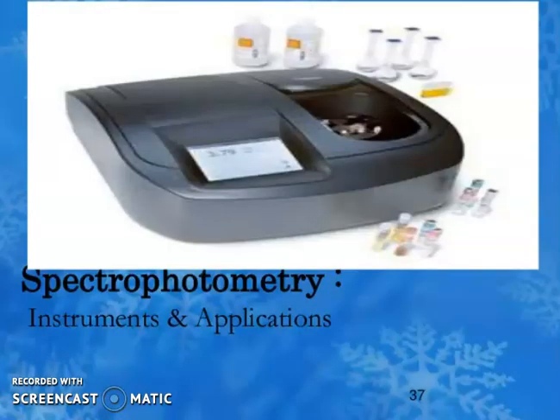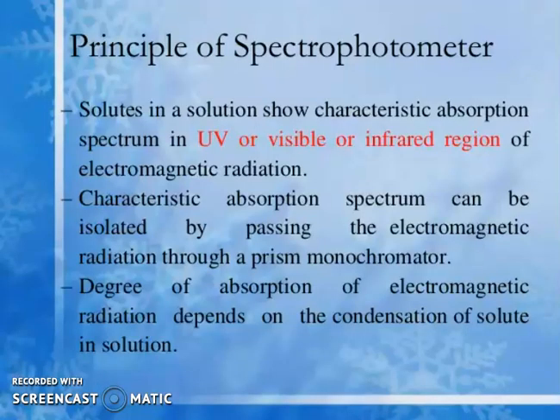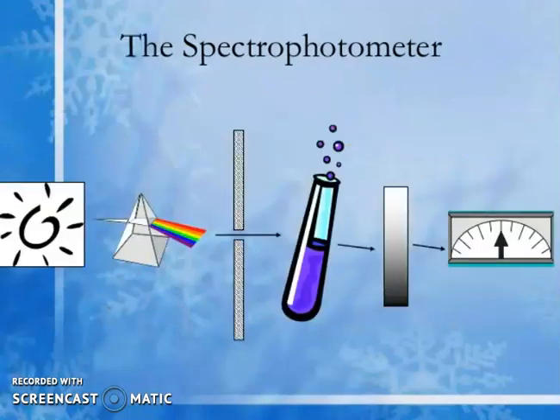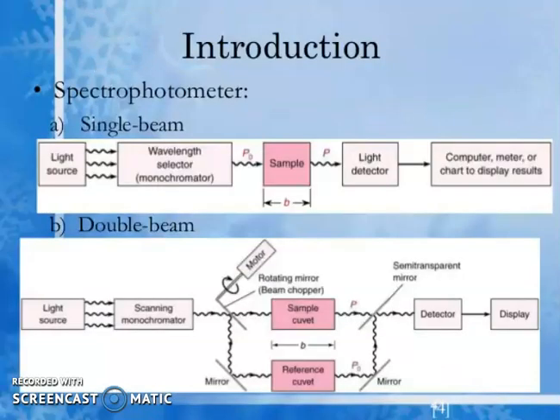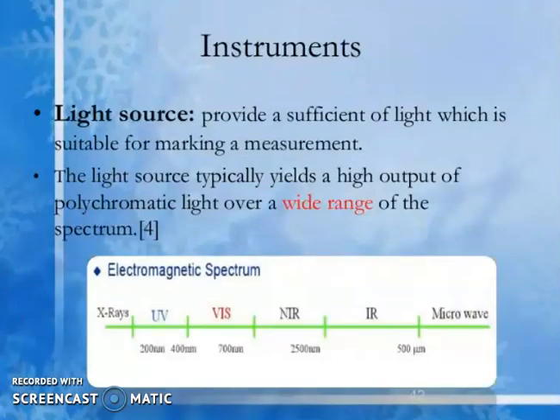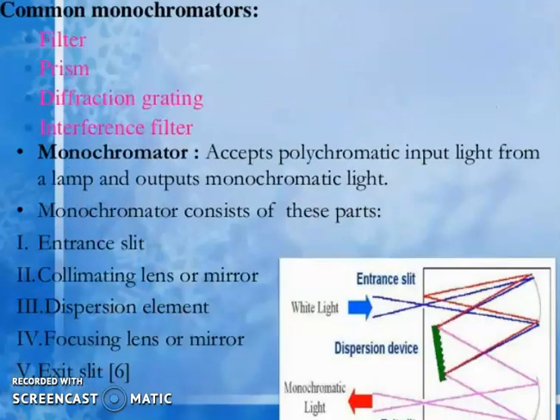Spectrophotometer — instruments and applications: the principle is that solutes in solution show a characteristic absorption spectrum in the UV, visible, or infrared regions of the electromagnetic radiation. The characteristic absorption spectrum can be isolated by passing radiation through a prism monochromator. The degree of absorption depends on the concentration of the solute. The spectrophotometer includes a display and controls, sample compartment, source, monochromator, and detector. Instrumentation types include single beam and double beam. The light source provides sufficient polychromatic light over a wide range of the spectrum.